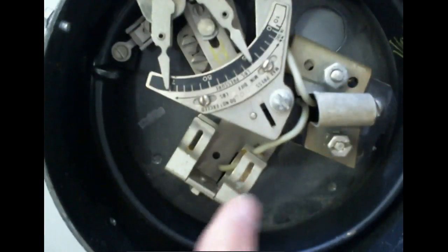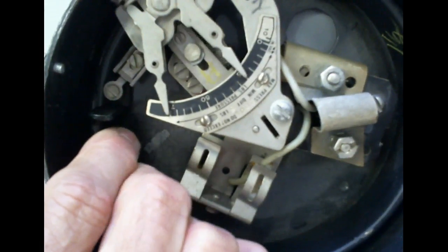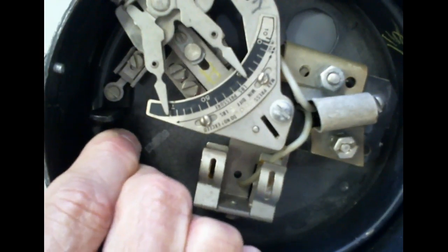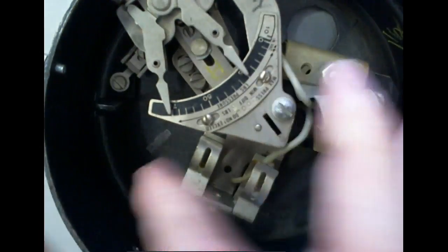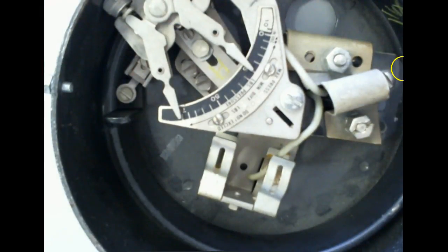Here's where the mercury switch is mounted. And of course, when we put pressure into it, it causes it to do what? Positive pressure would cause it to expand. And this is against the dead stop, by the way, but you could also use these to measure a vacuum. So positive pressure causes it to try to straighten out. Negative pressure would cause it to bend back together.